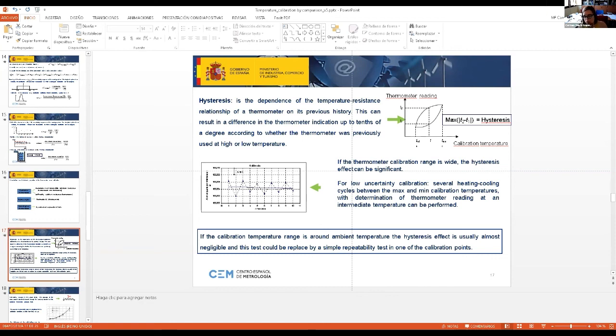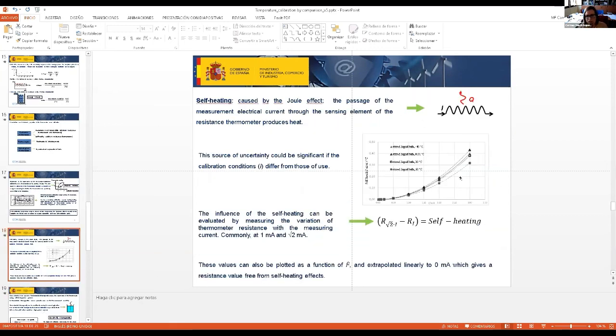It means that when a thermometer is exposed to a very high temperature, and then to a very low temperature, the reading at the very low temperature is influenced by the previous history of the thermometer. The self-heating. We are talking about resistance thermometers and resistance measurements. It's impossible to perform resistance measurements without passing current through the resistance, okay? When a current passes through a resistance, some heat is released due to the Joule effect, and this changes the temperature. This needs to be evaluated.